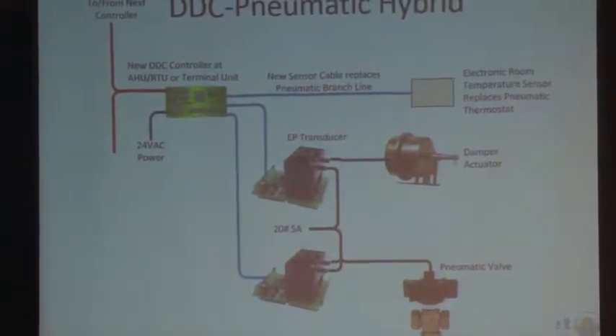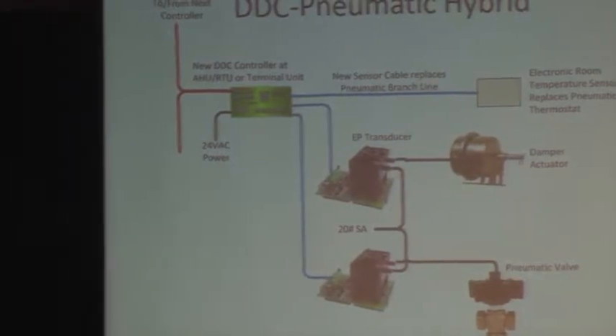Some of the problems with this is you have to keep your pneumatic control system. You have to keep your pneumatics, your compressor, air dryer, and air filters, all of which have to stay and continue to run. The real benefits, though, come if you have very, very large damper actuators because you need a lot of torque, same thing for really large valves, or if you have some actuation that has to be extremely fast, going from fully closed to fully open in just a second or two, and it's big. Well, it's almost impossible to do that with electric actuators. You can get them, but they're expensive. So those are some of the conditions where you may want to go with a DDC and pneumatic hybrid.